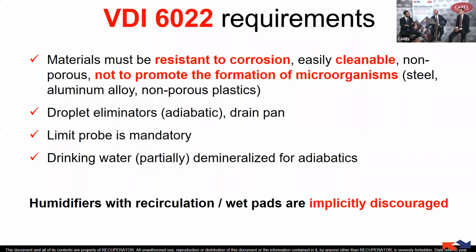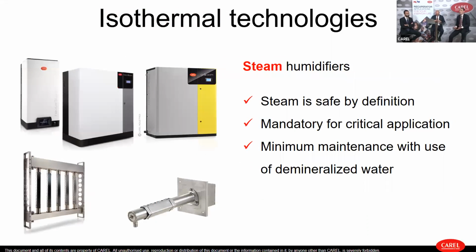Another important thing is that traditional humidifiers with recirculation or wet pads are implicitly discouraged by the norm. So the norm suggests using a humidification system that is able to introduce steam, which is hygienically safe, or fresh water, but not systems that use recirculation or wet pads. So which technologies can we use in order to fulfill these requirements given by the VDI?